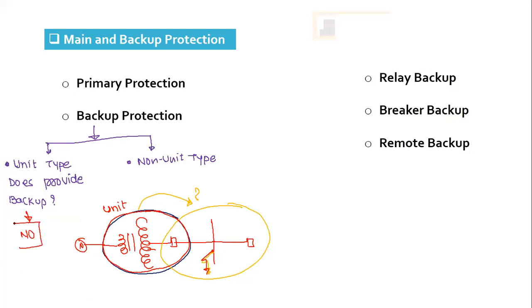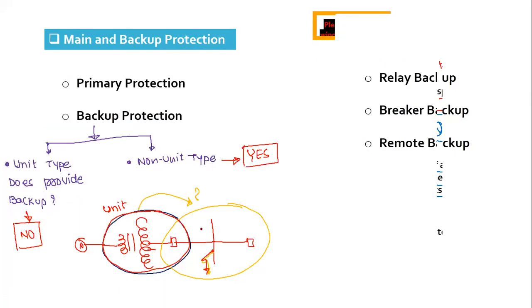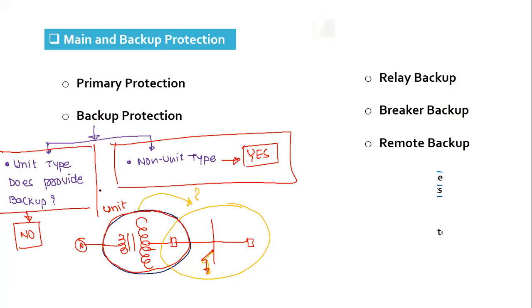So what is a unit protection scheme? They will never provide backup to any other scheme. Whereas a non-unit protection scheme will provide backup, because it will also respond, just as in the case we discussed, where this provides backup to this. However, there is no backup provided by any unit scheme. So this is also important: unit protection does not provide backup to anyone, whereas non-unit protection is required. In order to have backup in your system, you require a non-unit protection scheme also. So that is why we have a combination of these two.